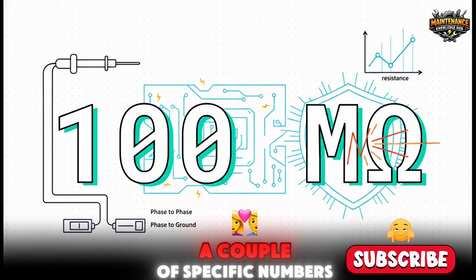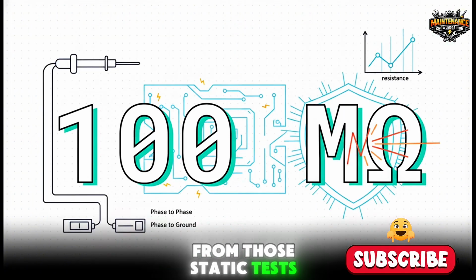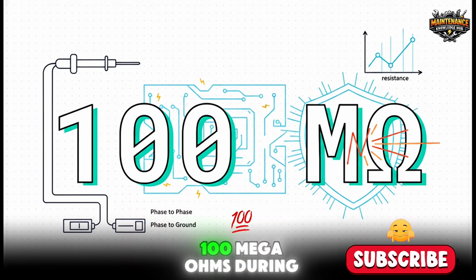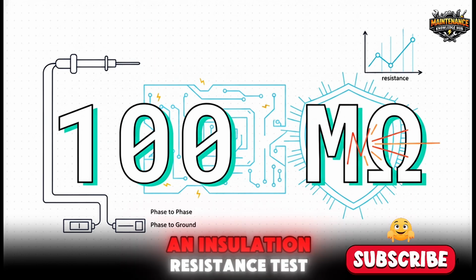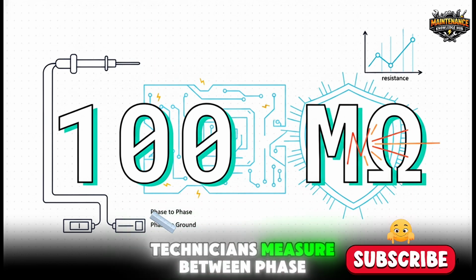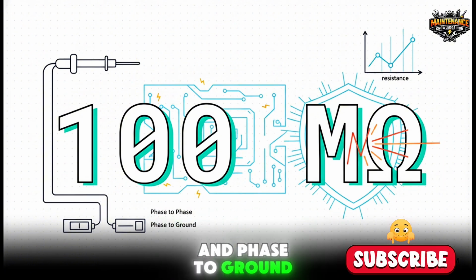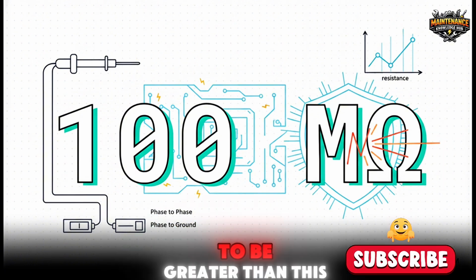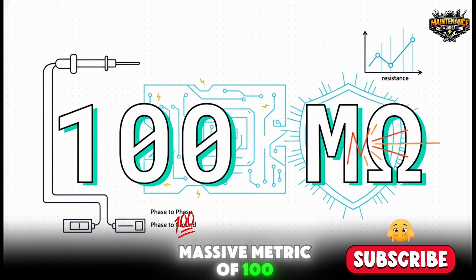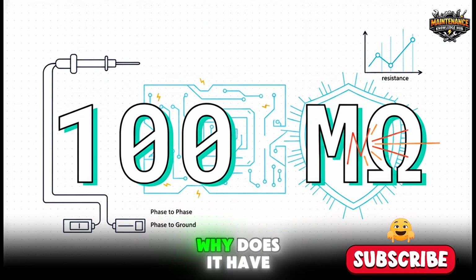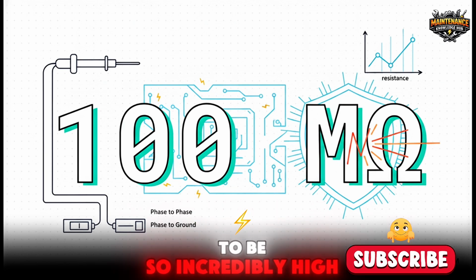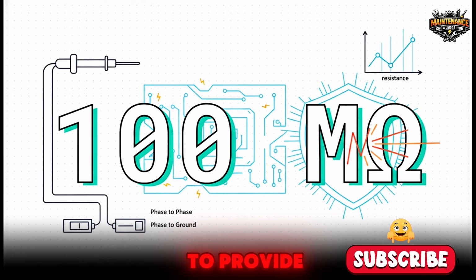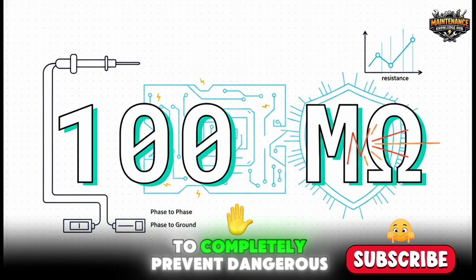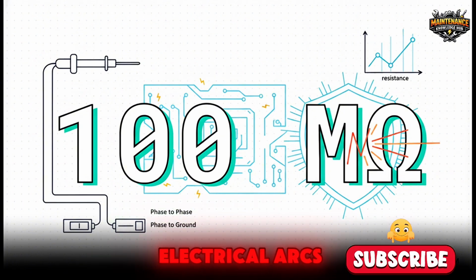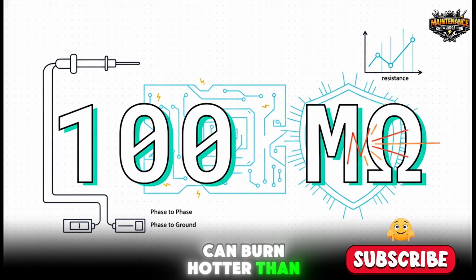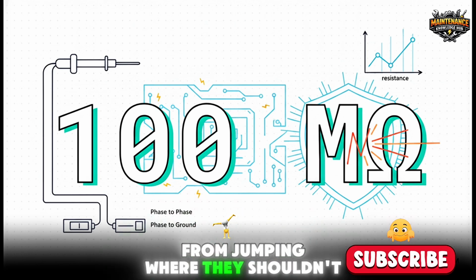Okay, let's look at a couple of specific numbers from those static tests, starting with this one, 100 megaohms. During an insulation resistance test, technicians measure between phase-to-phase and phase-to-ground. Typical passing values have to be greater than this massive metric of 100 megaohms. You might be wondering, why does it have to be so incredibly high? Well, because the insulation needs to provide unbelievable resistance to completely prevent dangerous electrical arcs, which, by the way, can burn hotter than the surface of the sun, from jumping where they shouldn't.